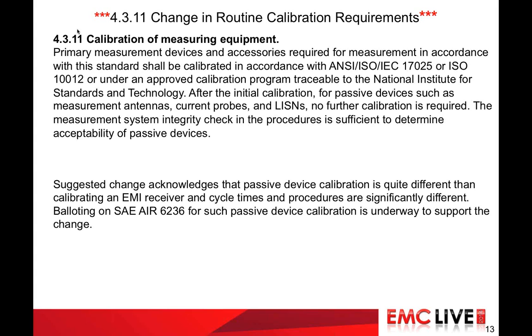But items such as attenuators, cable loss, current probes, LISN impedance, even ground antenna bases and low noise amplifiers are all easily checked in-house and are verified in each measurement system integrity check. Antennas can also be checked. It is important to note that checking a transducer's factor is not the same as calibration.